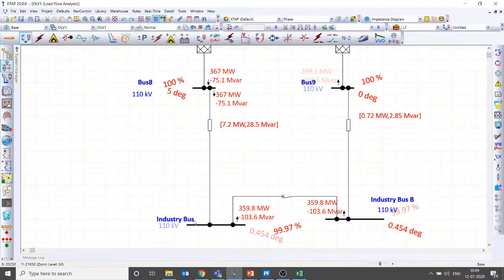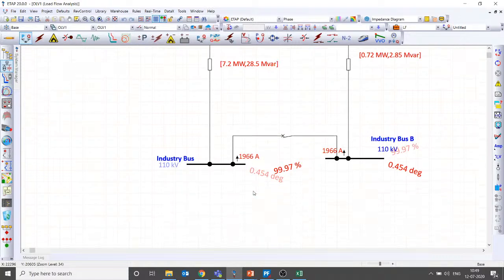Your bus bar of that industry substation may not be capable of handling this much current, right? If you plot it in current, around 2000 amps will flow via your industry bus, which is not feeding your industry loads. Your industry loads will be at 110 kV and 11 kV, and you will be feeding these loads, and you may not have sized this industry bus bar to be capable of carrying this power flow along this transmission. Your industry substation is basically designed to meet the loads of the industry, maybe 25 MVA or 50 MVA, so the current will be quite less.